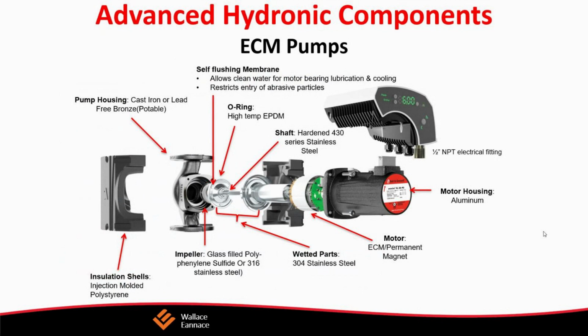You can adjust the pump. I've used them where you can actually adjust the pump for exactly the amount of flow that you desire. You can see exactly how much energy is consumed in watts, all readable directly from the screen. It delivers the right performance across a broad range of head and flow requirements due to the variable frequency drive.